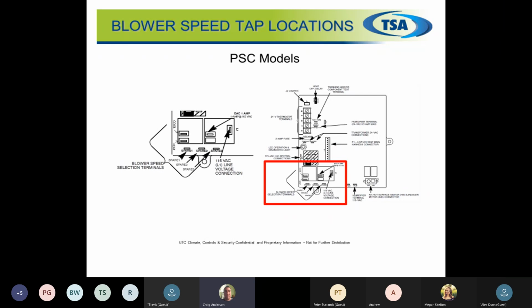Always check the board and always check the taps on the motor. See if we have the same power at the start and at the finish. Always check your power to neutral and always check your power to ground to see if the readings are the same. If we don't have the same reading from power to ground and power to neutral, then we need to look outside the box. Do we have a grounding problem or do we have a neutral problem? Things to look at.